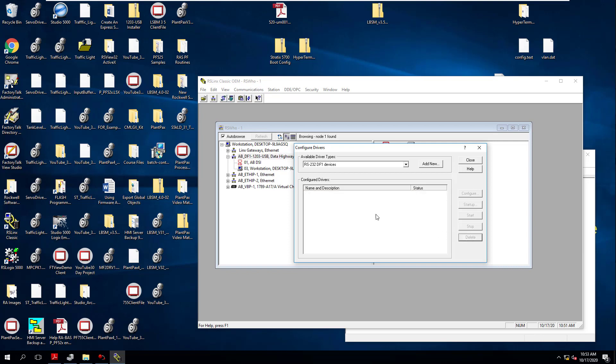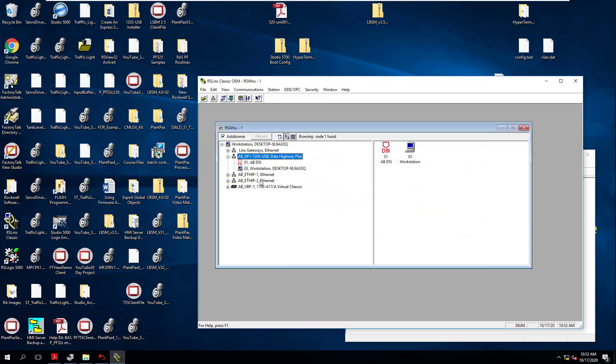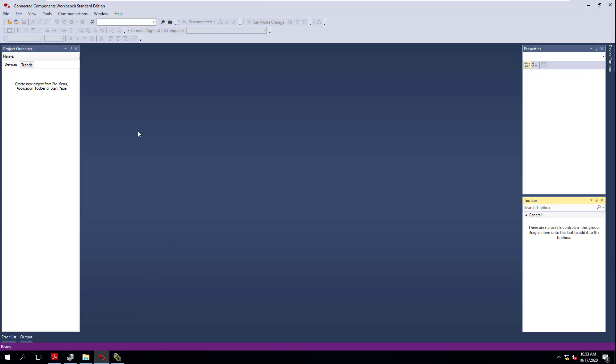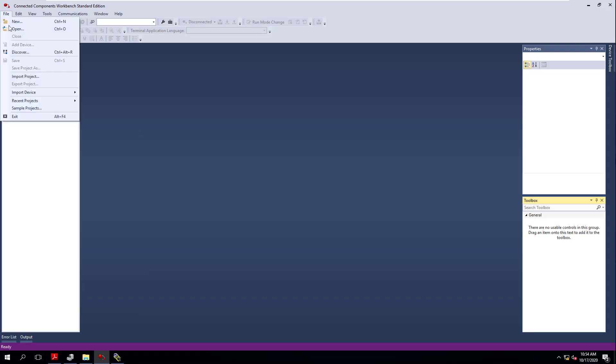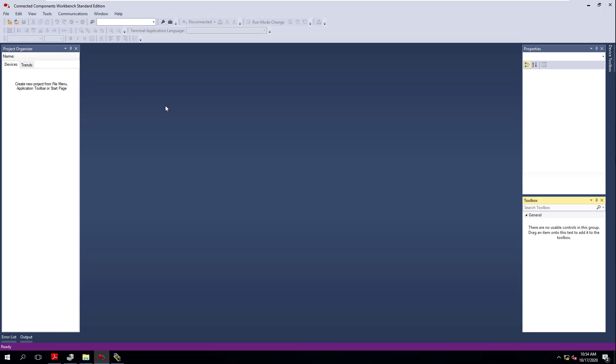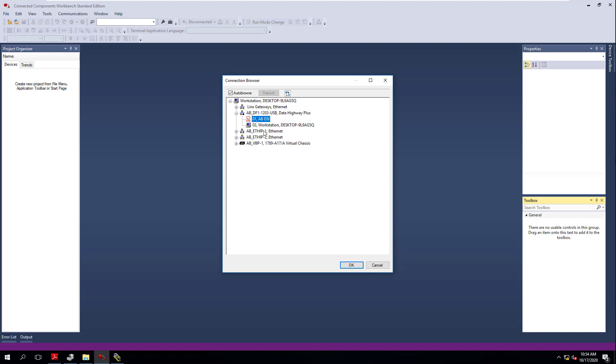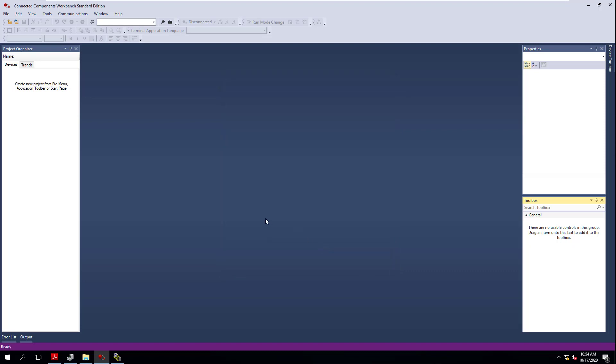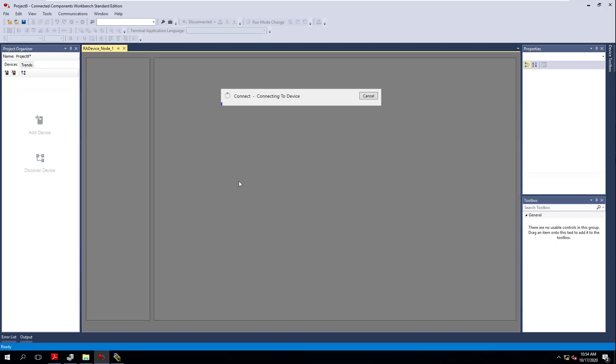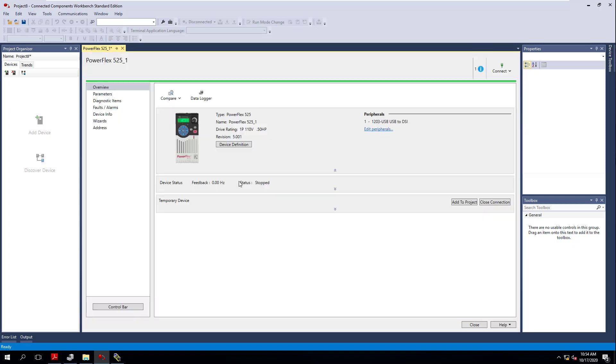We have our RSLinx driver with everything compatible and done. You're going to see ABDSI. You're not going to see your device right now. You're not going to see that I've actually connected to a PowerFlex 525 until you use Connected Components. We're going to go to Connected Components, go to our file, and hit discover. In the top left corner, you're going to hit discover. You're going to use your new driver that you just made. We're going to select the ABDSI that we just clicked. Now we're actually connecting to our device. This is getting the PowerFlex information and uploading it.